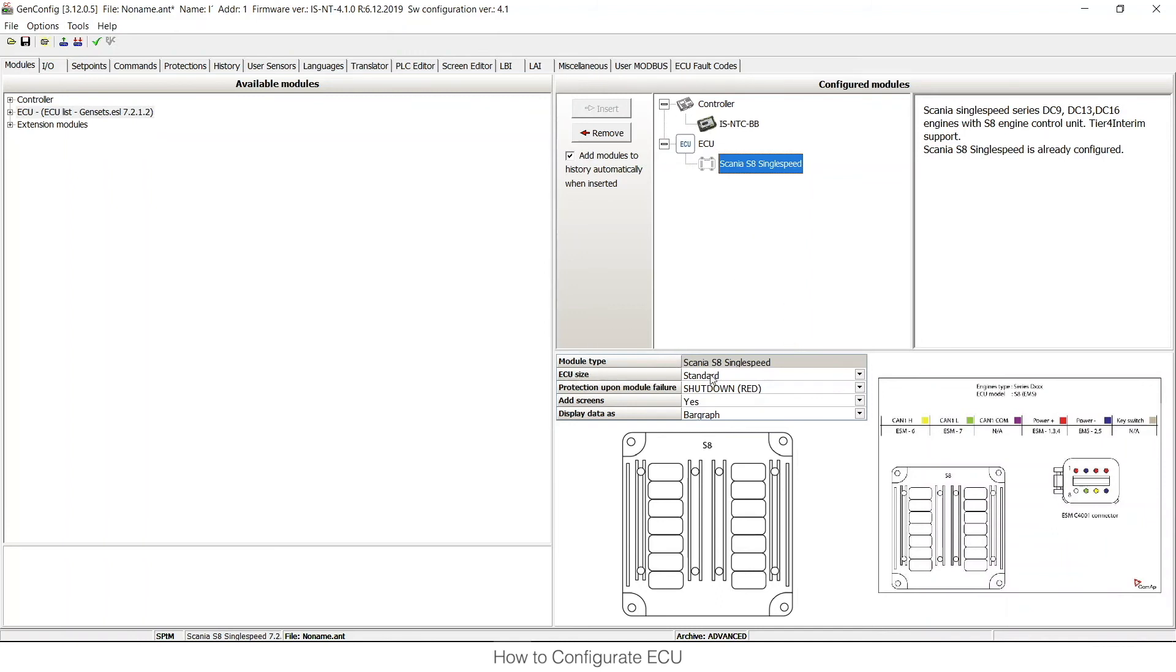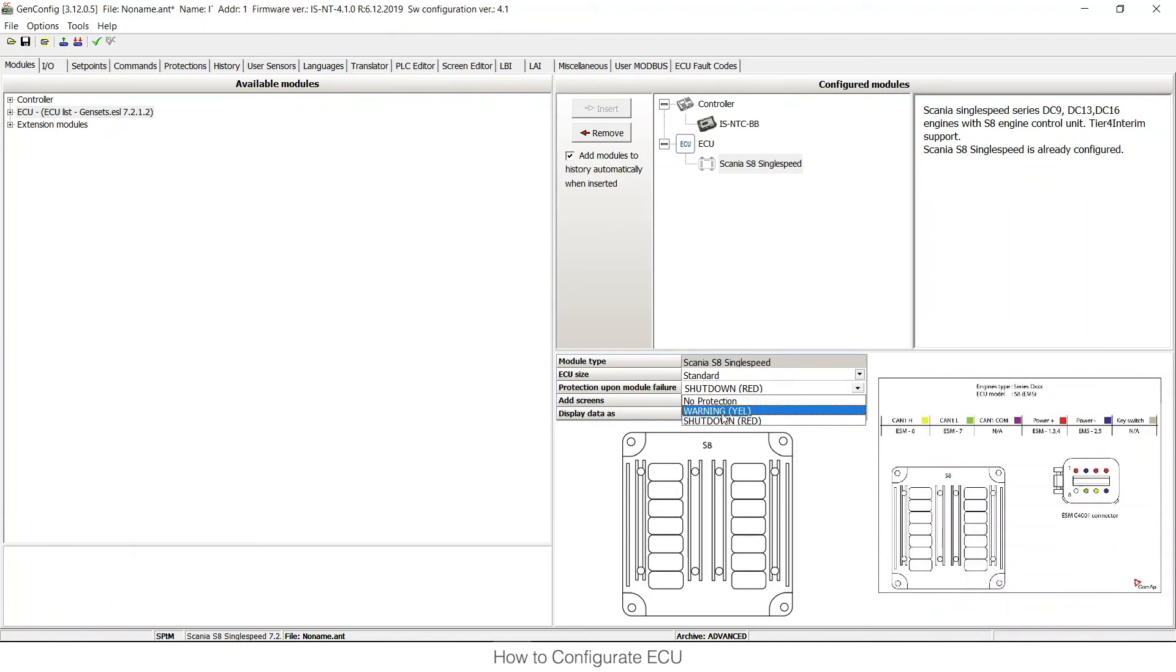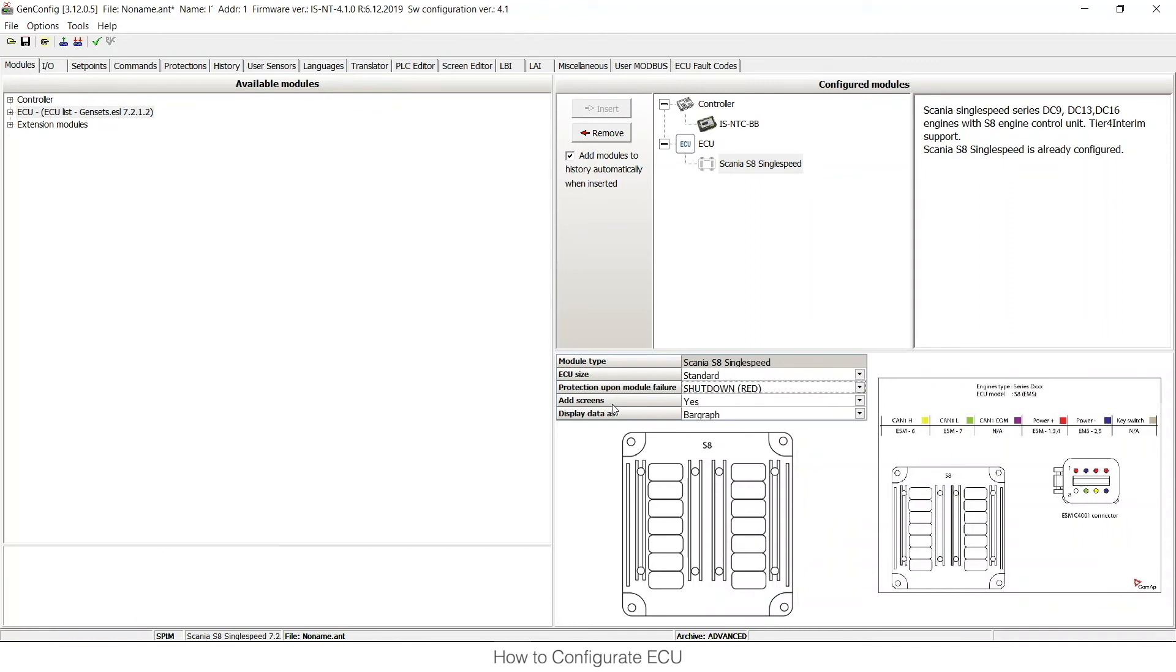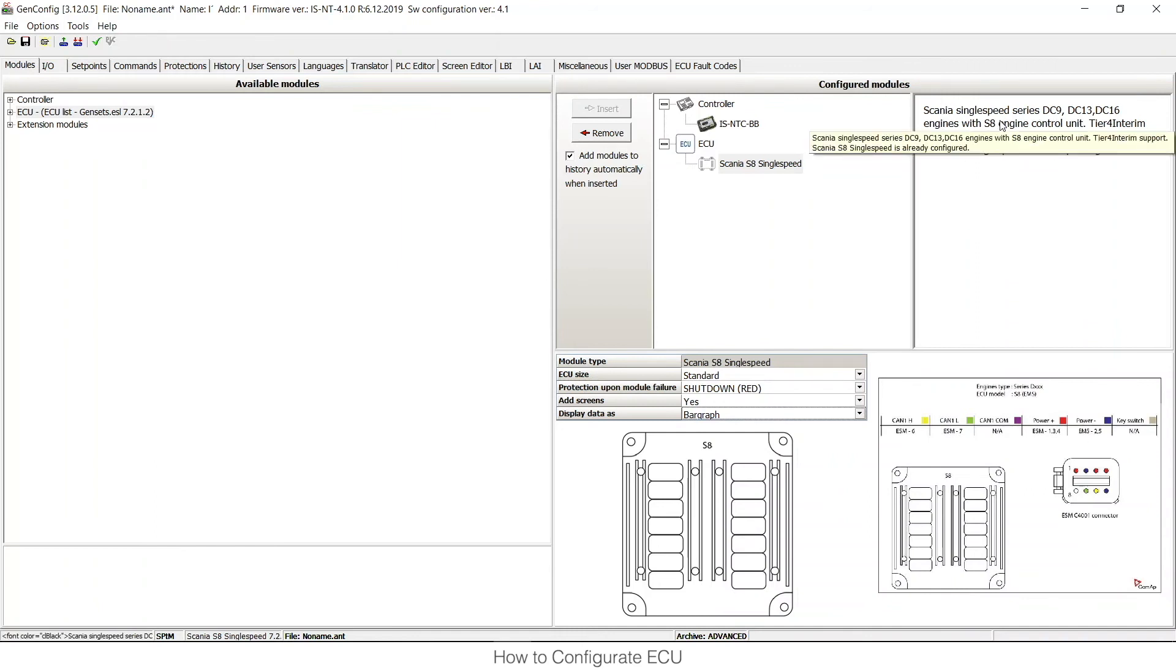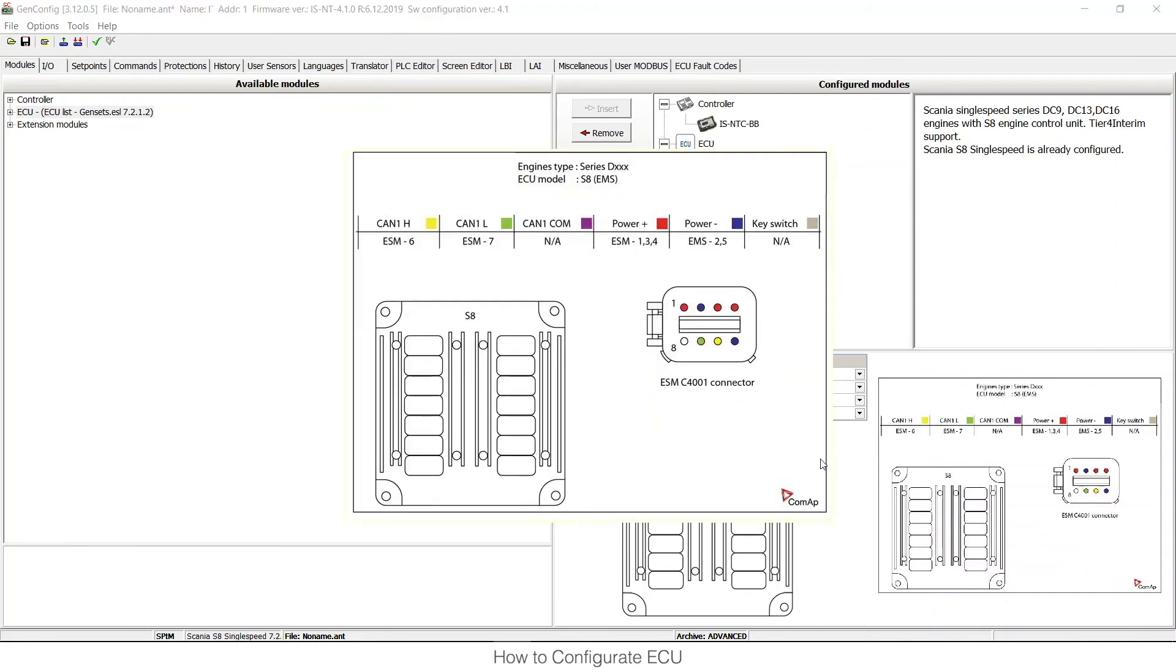I can choose the ECU size. I can choose what will happen upon module failure. This means if the communication is lost whether I would like to have first level or second level protection or no protection at all. I can choose whether I would like to add screens of all the ECU values available onto our displays. And I can choose whether I would like to display this data just as numbers or bar graphs. You can see that there is a small hint for which engines this ECU is typically used. You can double click on this image and you can see the detail of how this is wired.